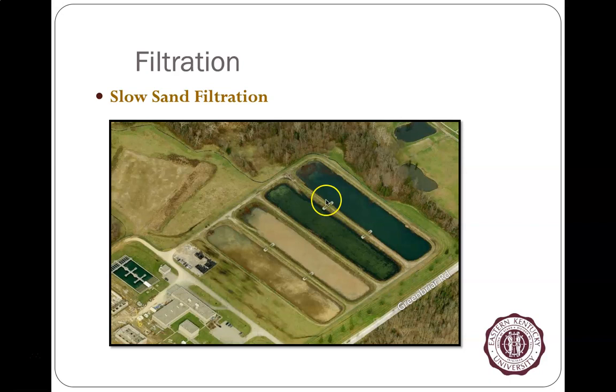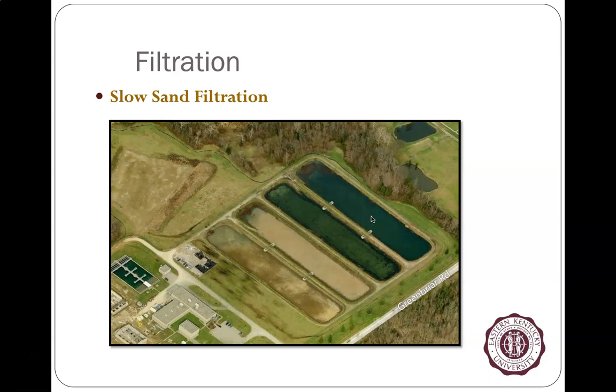Here's an example showing a sedimentation basin alongside what is required to do slow sand filtration. It takes a long time for the water to pass through. One basin — and possibly another — is being actively used, where clear water from the sedimentation basin flows on top of the sand. Over time it finds its way through the sand into an underground clear well, where it's ready to be disinfected. A third basin has been used and is drying out — you can see the muddiness of it.